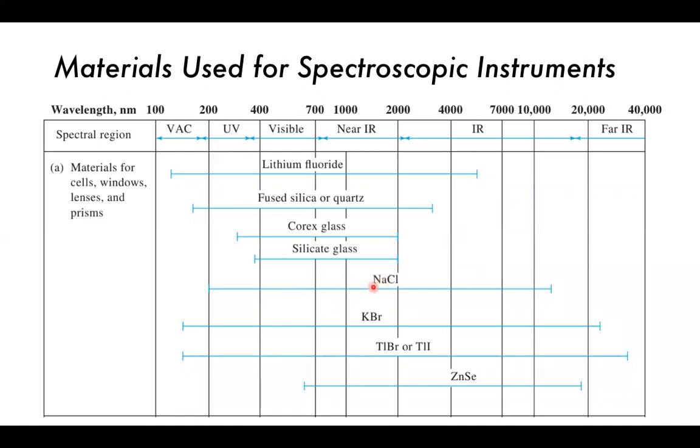So the issue there is that it cannot be used for measurements of anything which is aqueous. A lot of things are aqueous solutions. So we can't use these for that, but we can use these for things like organic solvents or other things like that.